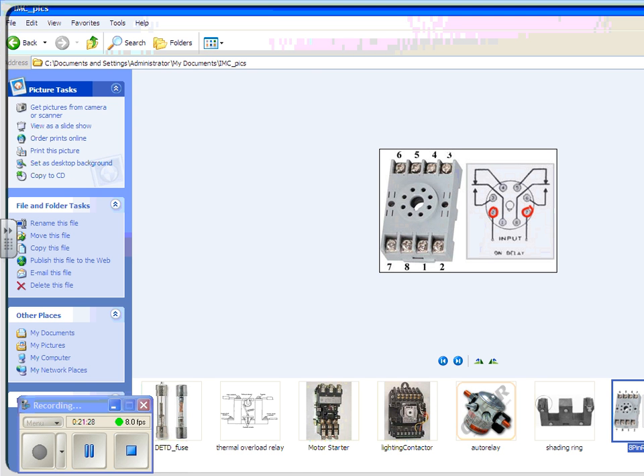All right, simple stuff. So anytime you have a block, usually they have markings on what everything is. You notice on this one, we have a common pin, which is 1, and another common pin, which is what? 11. No, this is 8. Sorry, this is an 8-pin. So it's the first and the last that are the common pins for the normally open, normally closed. And you notice that we have a normally closed up here on 4 and 5, and we have normally open on 3 and 6. So 8 pins are always laid out like this.